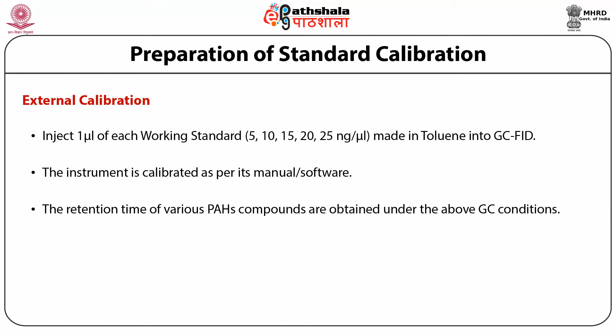The sample injection is carried out by taking 2 microliter of sample from the amber vial using a standard gas-tight syringe and injecting it into the capillary GC-FID instrument for analysis. Record the resulting concentration of each polyaromatic hydrocarbon compound including benzopyrene. A 10 nanogram per microliter concentration of benzopyrene or the other polyaromatic hydrocarbon standards is to be injected in the GC-FID instrument with every batch of samples. As the control, internal standard of 10 nanogram per microliter concentration is added to each sample prior to the analysis in case internal calibration is used.